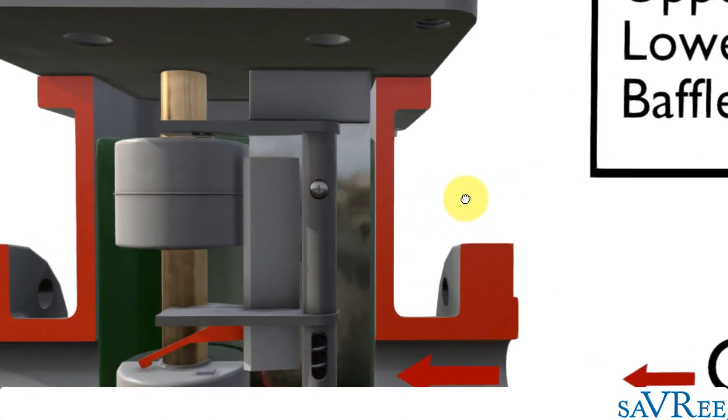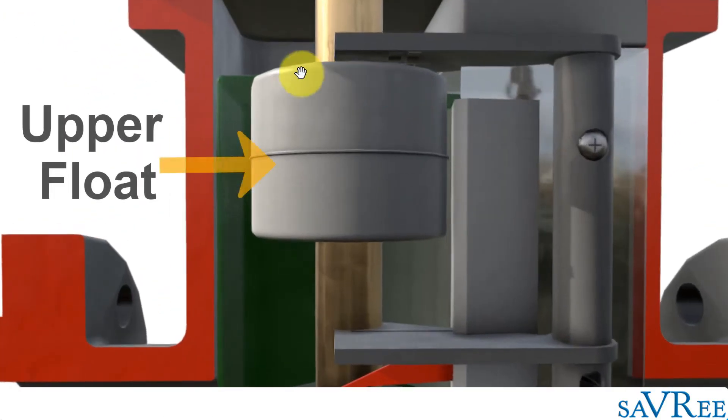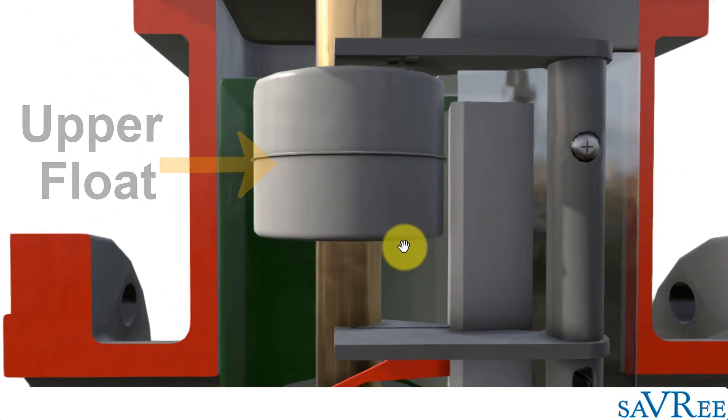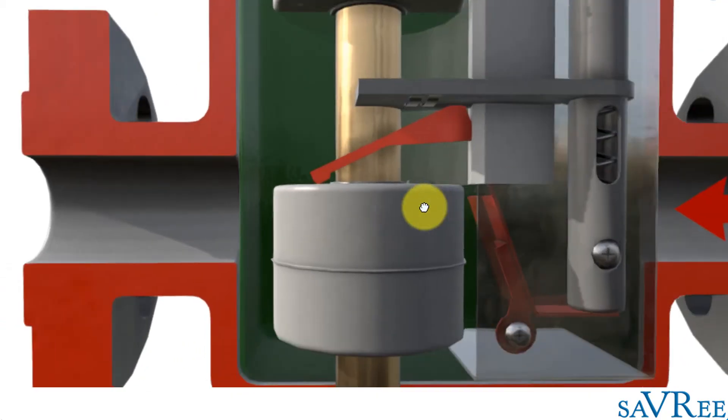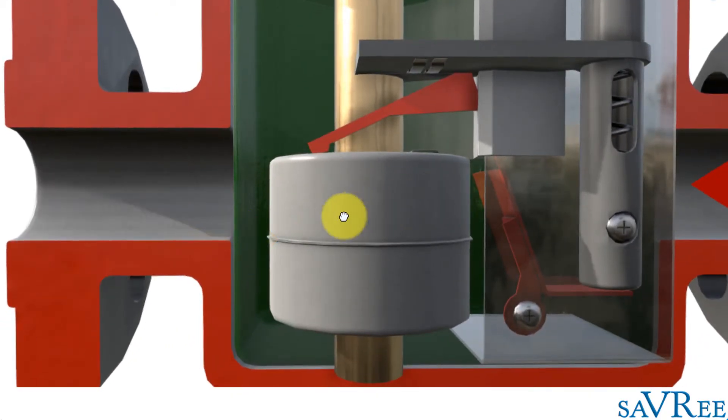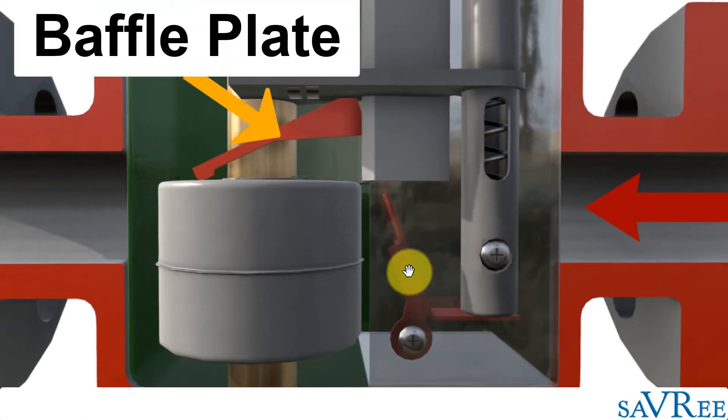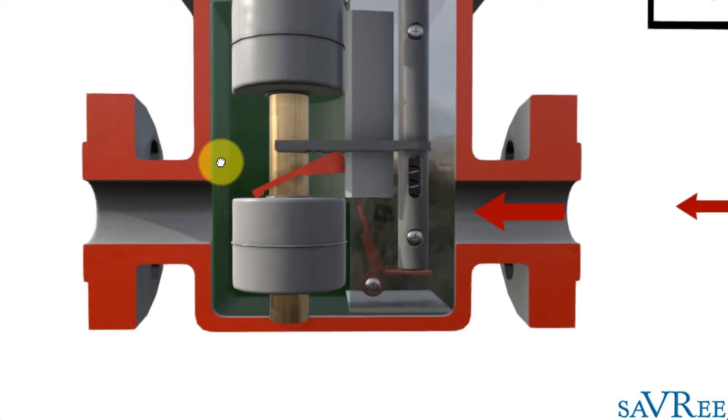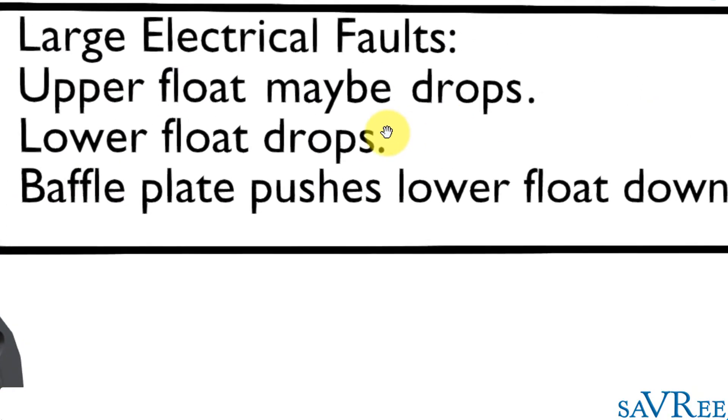Let's have a look how the Buchholz relay protects against this type of situation. We've got an upper float, which is this one here. We've got a lower float, which is this one here. And then we've got a baffle plate, which is this red thing pushing the lower float down here.